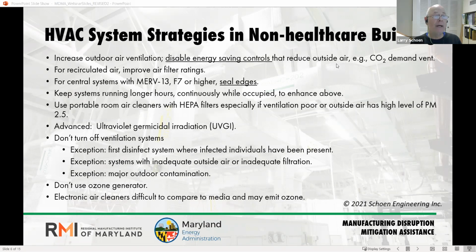So if you have an old air handling system that might have only a 1-inch filter rack and you can't get a MERV 13, MERV 11, even MERV 8 or 9, do it. It improves the filtration. And the underlying language in the third bullet: if you put in a higher level of filtration and you have gaps around the edge, you are defeating your purpose. So seal the edges of those filters, either with a tight-fitting cardboard to metal surface, or in some cases, a piece of spring metal, or even weather stripping. Foam weather stripping will do a good job.